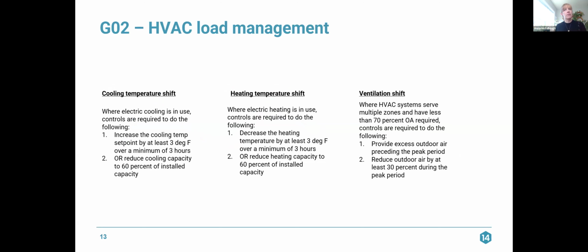So the requirements of each of these: a cooling temperature shift, where electric cooling is in use, requires controls to increase the cooling temperature set point by at least 3 degrees over a minimum of 3 hours, or reduce the total cooling capacity to 60% of the installed capacity. Where you have electric heating, controls are required to decrease the heating temperature by at least 3 degrees over a minimum of 3 hours, or reduce the heating capacity to 60% of the installed capacity.